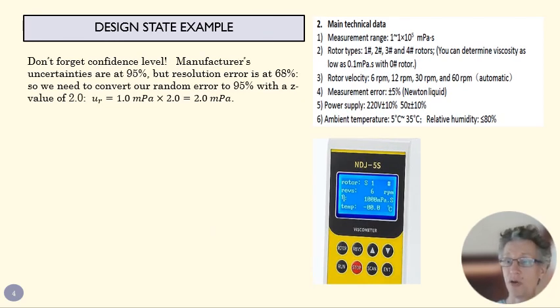But I want to make sure that I consider units and confidence level. Now they're in the same units, they're both in millipascals, but they're not at the same confidence level. Manufacturers' uncertainties we can assume are at 95%, at 2 sigma. But resolution error is going to be just at 68%, at 1 sigma. So we want to change that resolution error to get up to 95%, because that's what engineers use most of the time.